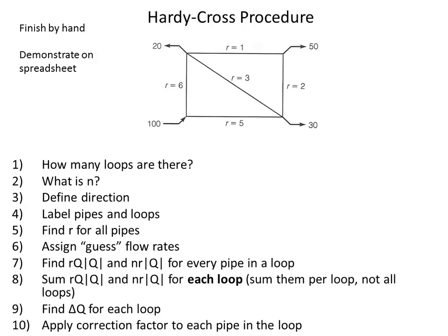I think there's one more that we really got to remind ourselves because it's such a common mistake when we do the Hardy-Cross procedure. In fact, I'd say it's the most common mistake that students make. Bert? Just not flipping the sign when you go back and forth. Right. Flip sign. Is it for every pipe? No, it's flip sign for common pipe between two loops.